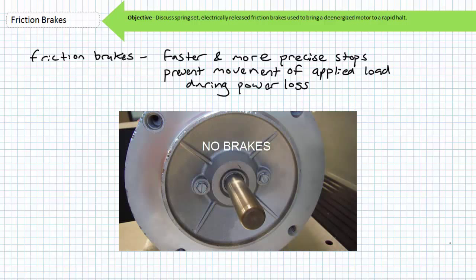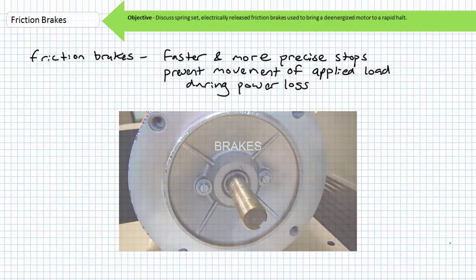A de-energized motor ordinarily free spins to a halt. Friction brakes, in contrast, are used to bring a de-energized motor to a rapid halt. Friction brakes can therefore provide a faster and more precise means of stopping a motor. Additionally, friction brakes serve to secure the shaft and applied load of a de-energized motor. Applications for friction brakes include lifting and securing objects against the force of gravity and preventing the applied load from movement during power loss.